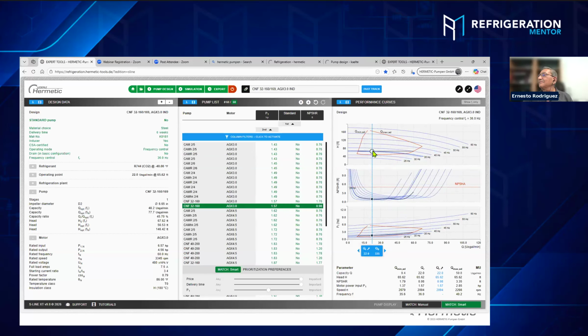I would like to use this pump because at 36 hertz, you can see it is inside the red area. So we're trying to get inside the efficiency curve, but don't be too close. Yeah, don't be too close. Okay, this is the best application.